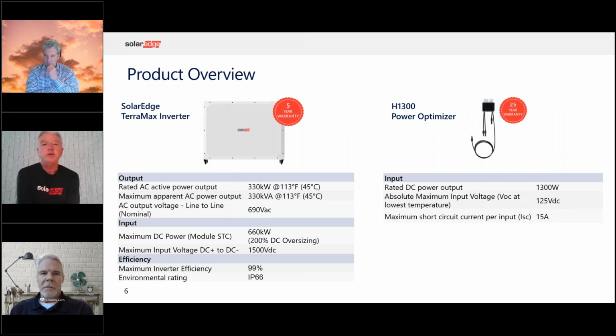Let's move on and look at some of the specifications of the TerraMax. Again, it's a 330 kilowatt inverter, rated at full power up to 45 degrees C. That's a higher full power rated inverter than you typically see in this class. Its max apparent power is 330 kVA, and its output voltage is 690 volts AC, so it's above 600 volts, in that 800 volt class of inverters.